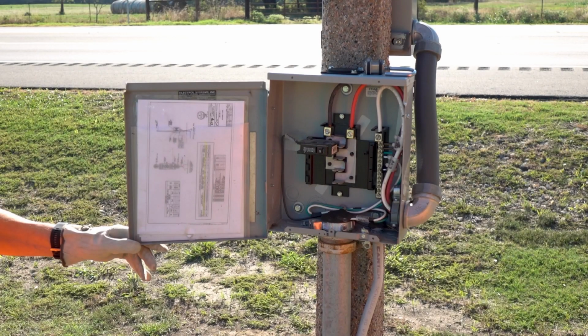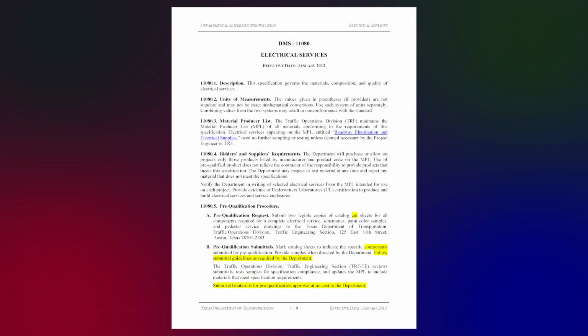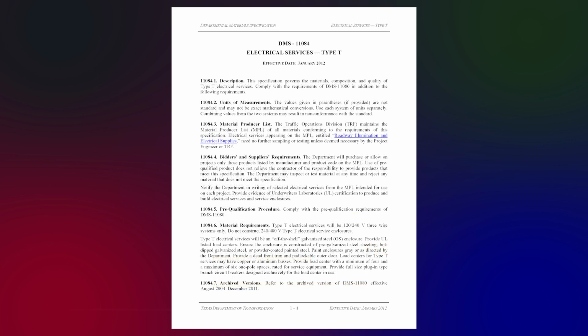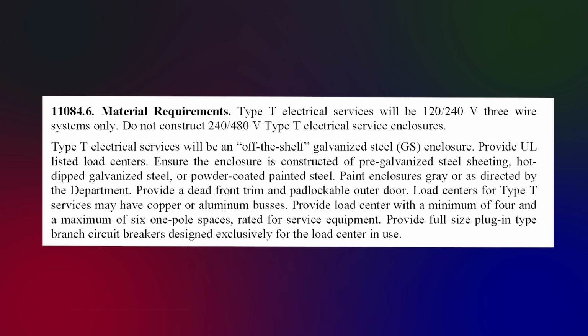Let us begin our inspection by looking first at the load center and its internal components. Departmental Material Specification DMS 11080 Electrical Services and DMS 11084 Electrical Services Type T lay out the specifications for this enclosure. To summarize these specifications, a Type T service uses a galvanized steel weatherproof enclosure, a UL-listed load center, has 4 to 6 breaker spaces, has copper or aluminum bus bars, and uses full-size plug-in breakers.